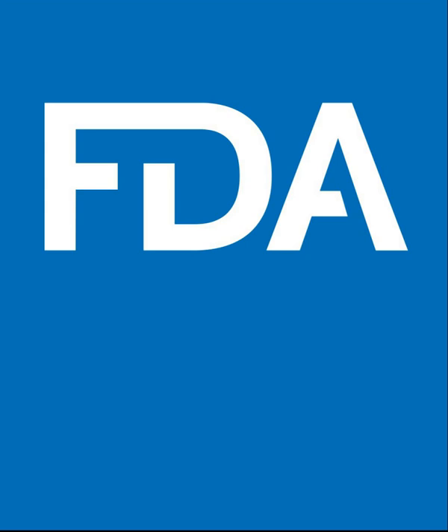Premarket Approval (PMA) is the most stringent type of device marketing application required by FDA. Unlike the 510(k) pathway, the maker of the medical device must submit an application to the FDA and must receive approval prior to marketing the device. The PMA application contains information about how the medical device was designed and how it is manufactured, as well as preclinical and clinical studies of the device, demonstrating that it is safe and effective for its intended use. Because the PMA requires a clinical trial, it is significantly more expensive than a 510(k).